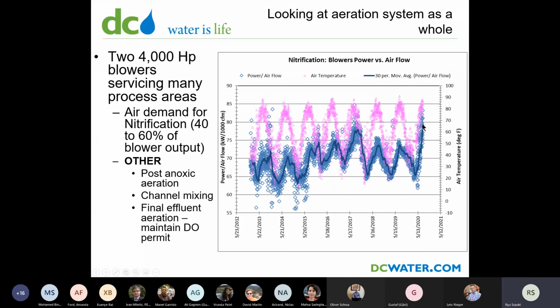And the reason for that is that this summer, where it seems like we have the poorest efficiency, also happens to be the summer where we required the least amount of air compared to previous years, and accordingly used the least amount of power in the blowers. But the problem with these old school centrifugal blowers that are not on a VFD is that as you try to turn down the blower as much as possible, you basically get a point of diminishing return.